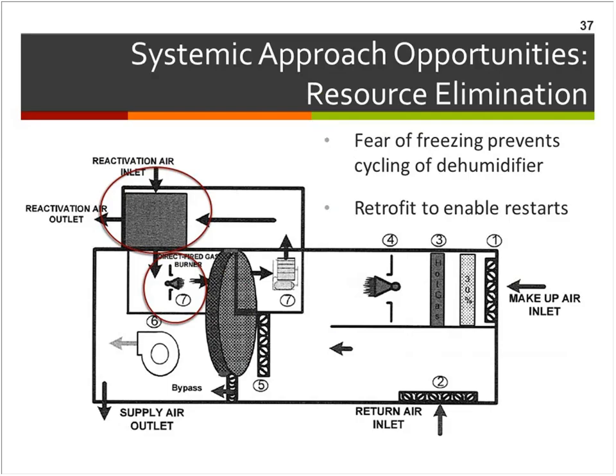They were afraid that a cold startup would essentially make the equipment unviable. So instead of running it all winter when the actual concern is just the startup process, we recommended retrofitting the unit so that 5 minutes before it starts up, an electric coil warms things up and eliminates the concern about the heat exchanger. So asking why and finding a different way leads to different solutions.